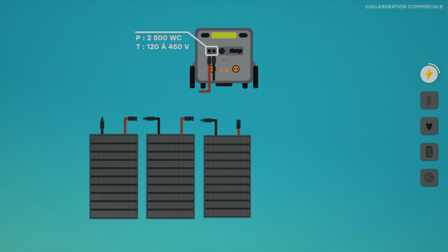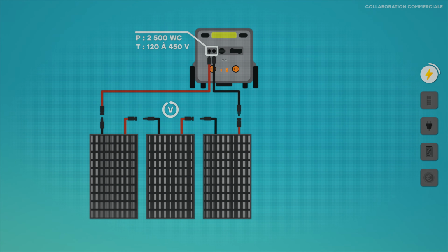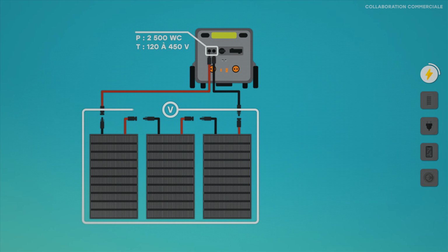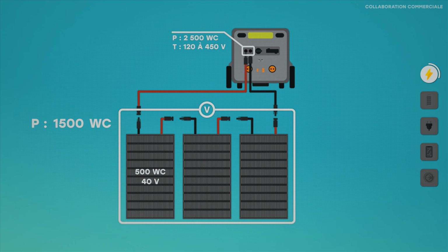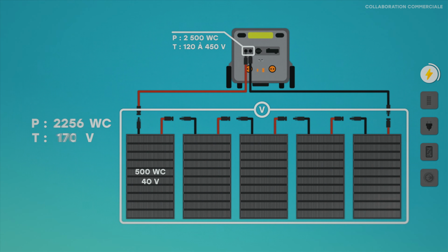In other words, you'll need to connect the solar panels in series so that the voltages add up. A 500 watt peak solar panel produces about 40 volts. So, at a minimum, you'll need to connect three 500 watt panels in series to get 1,500 watts peak power and 120 volts of voltage. And at most, you can connect five 500 watt peak panels in series to reach 2,500 watts peak and 200 volts.